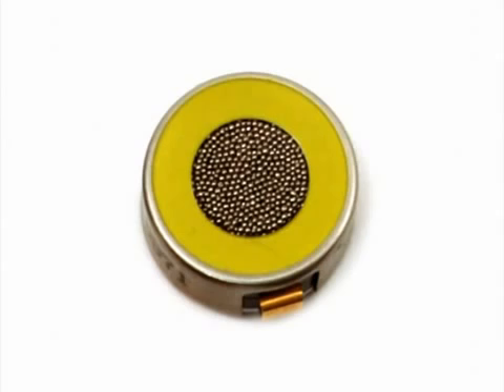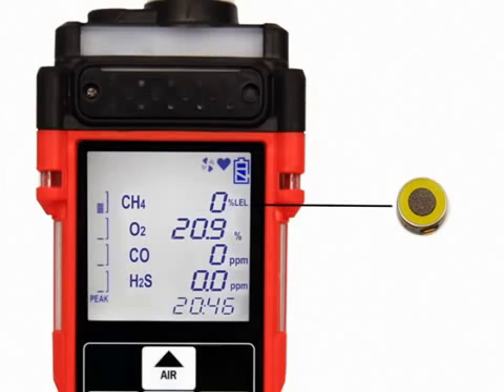A sintered metal flame arrestor covers the element and allows ambient air to diffuse into the sensor. The reaction of gas with oxygen on the catalyst causes a change in the resistance of the element, which affects the current flowing through it.